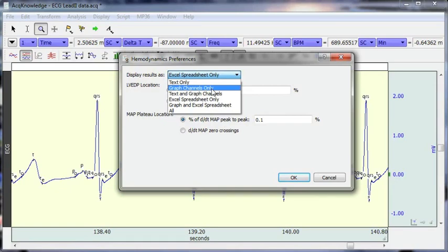For example, if you want to have a new channel for P height, select this option and the software will create a channel specifically for P height, and it will give you a value for each cycle that was recorded. You can obviously do both of them at the same time, down into the journal and also into graph channels. And then the same, instead of going to the journal file, you can paste into Excel, and again, both.